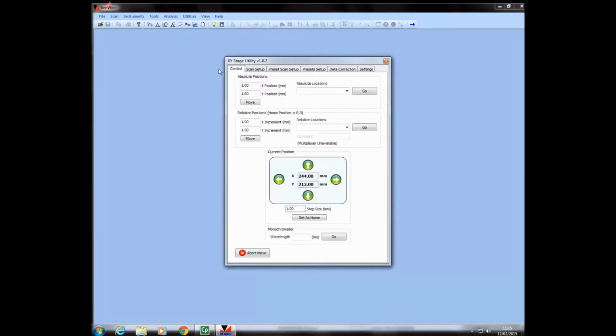Now, first we need to make sure that we calibrate the system. We should place the reference detector under the beam, and it's also useful to let some light be transmitted from the monochromator to ensure that the beam is aligned with the detector. In the specific case of the PV300XY, we must control the position of the detector using the XY stage utility. In a standard PV300 unit, we can simply move physically the detector mounted atop the detector point on the temperature controlled vacuum mount under the beam.